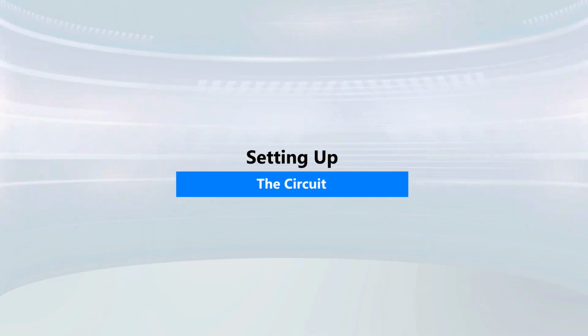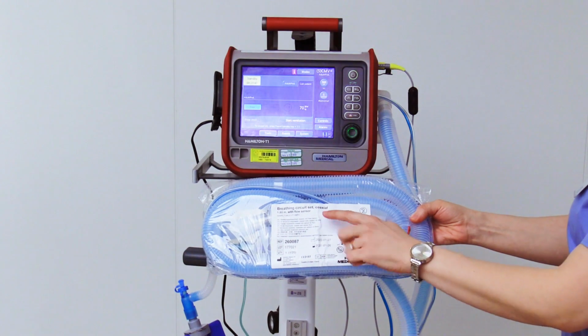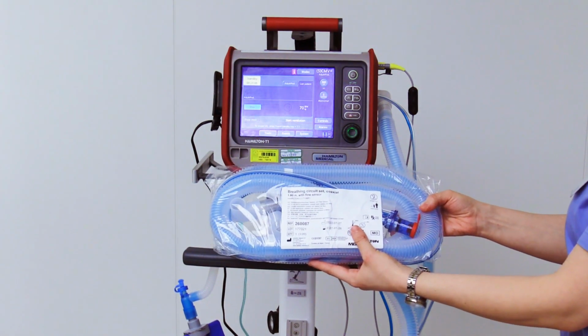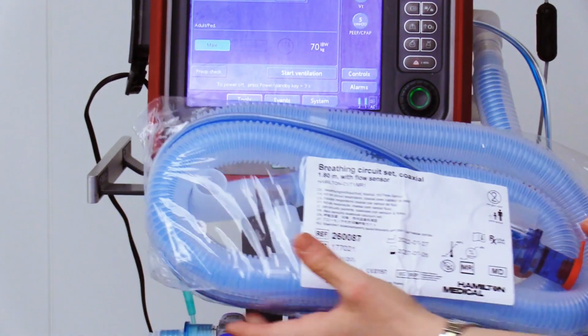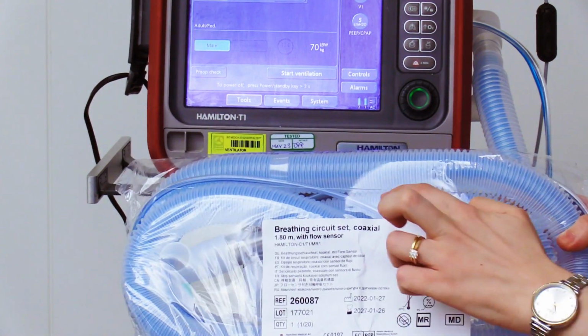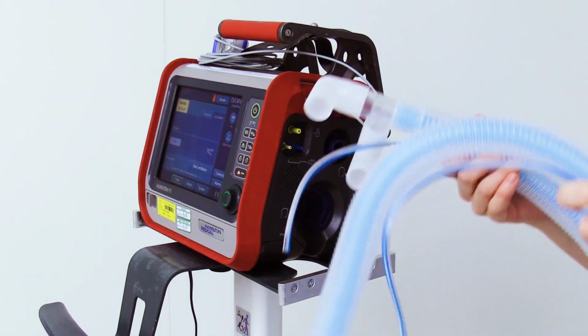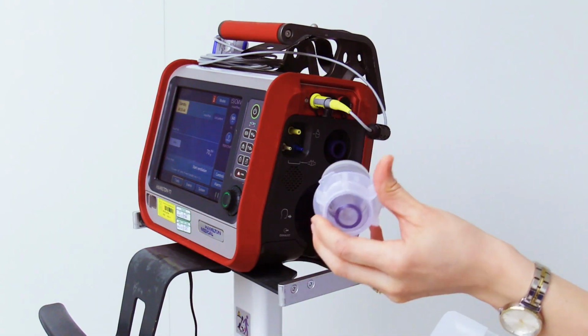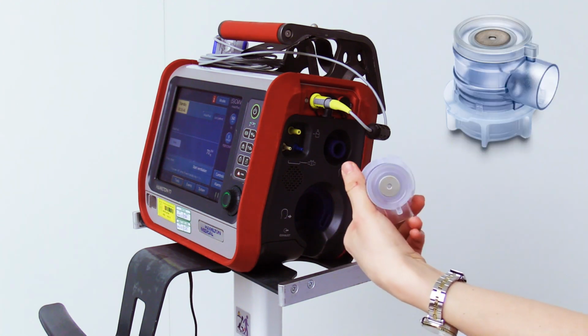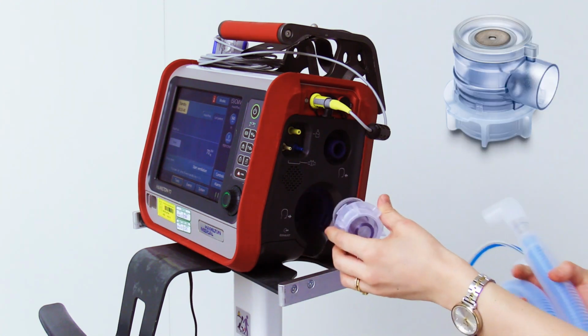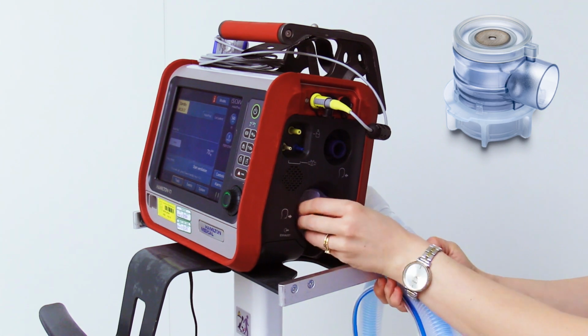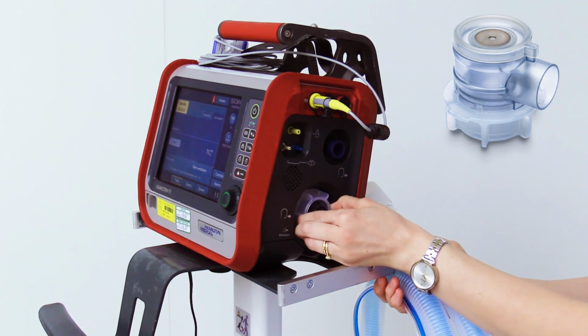Now, let's set up the circuit. The coaxial breathing circuit comes pre-assembled. In the packet, we find the circuit, the expiratory valve, and the flow sensor. To connect the breathing circuit, you need to first install the expiratory valve. Position the valve in the expiratory port and twist it clockwise until it locks into place.